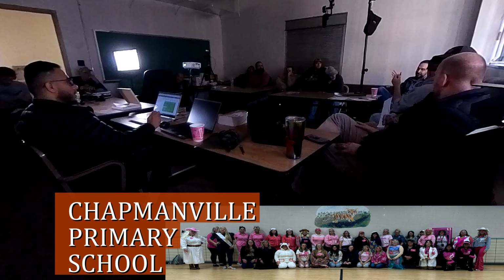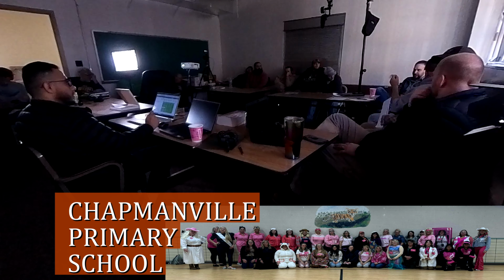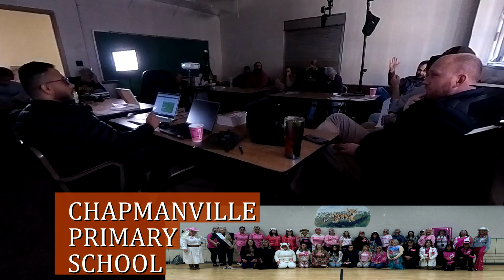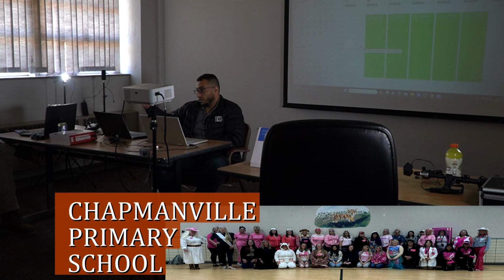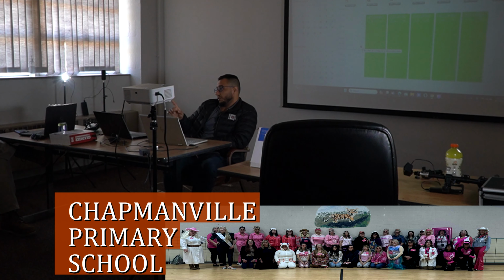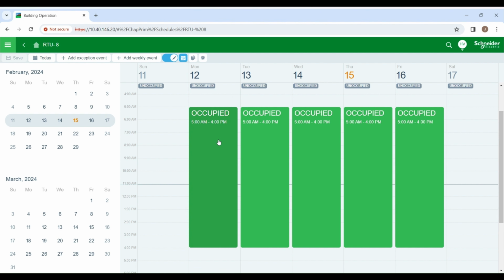If you have a snow day or something, you only have to do one entry on the calendar, and it'll do the entire school. That's right. The calendar will apply for this master. It will command all the individual schedules that we have. So here's your occupied time right now, from 5 a.m. to 4 p.m. You can see the green columns. This is where your time period has been specified.